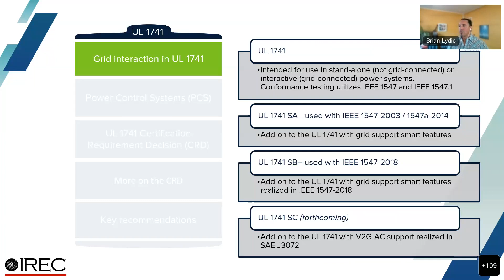But 1741 was initially published in 1999 and had updates in 2005 that required interactive inverters to conform to IEEE 1547-2003, and then the test standard for 1547, which is 1547.1, was published in 2005. So really the first time 1547 was implemented, it was through UL 1741 for the certification of inverters, and UL has maintained that throughout the last 18, 19 years, however long that's been.